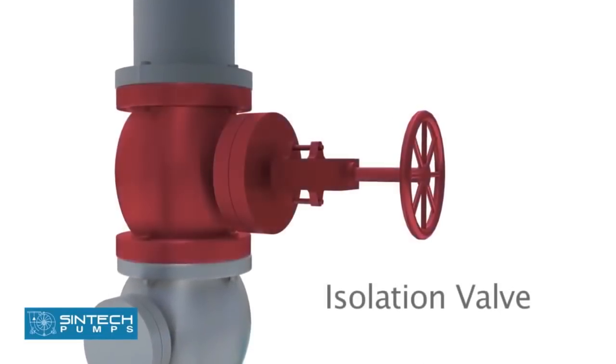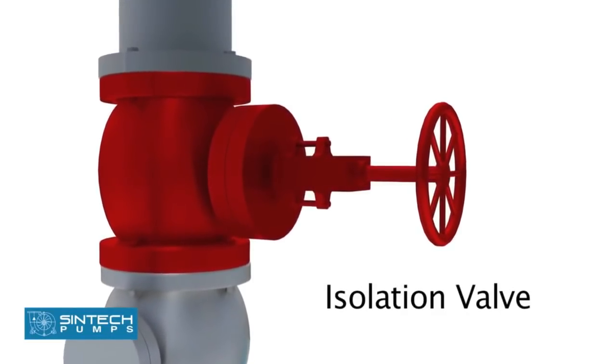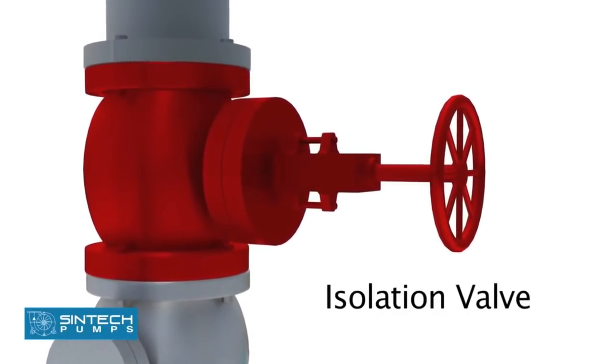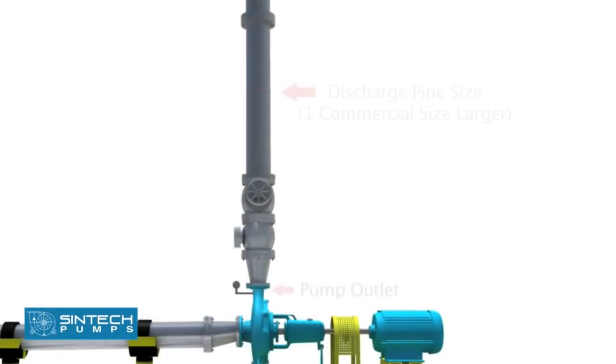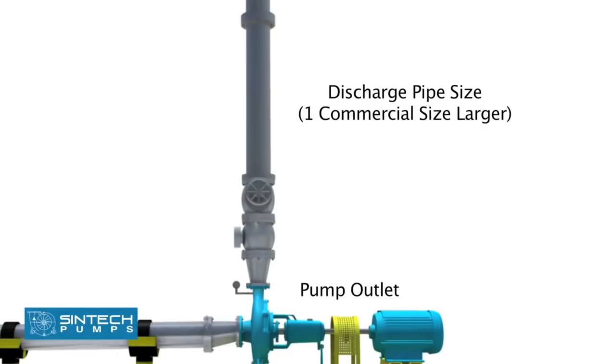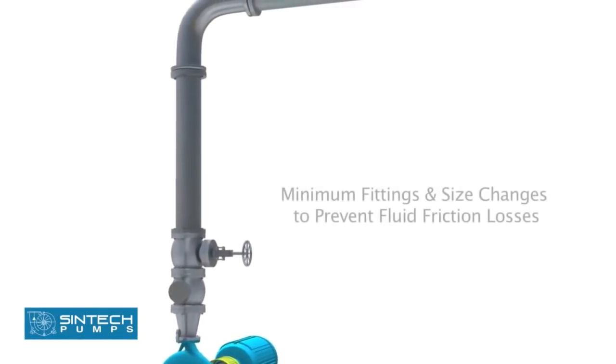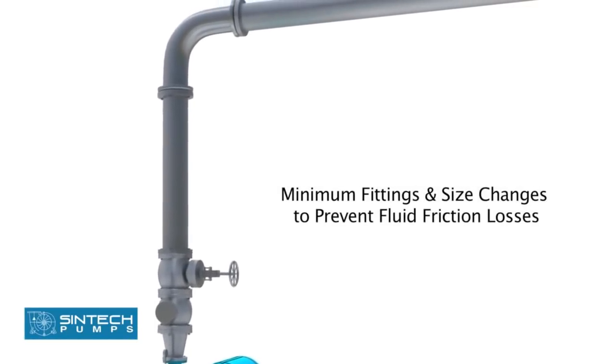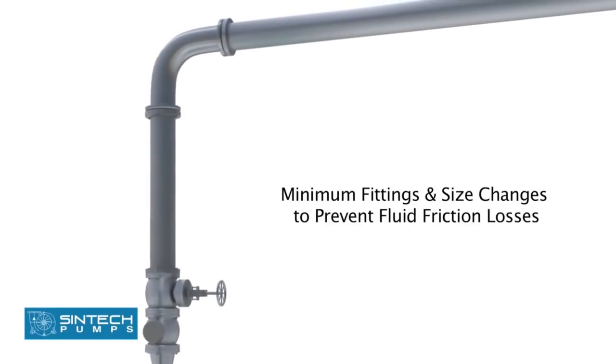The isolation valve is provided downstream of the check valve so that these can be taken up for servicing whenever required. Discharge pipe size should be at least one commercial size larger than the opening of the pump outlet. The number of fittings and size changes should be minimum to prevent fluid friction losses.